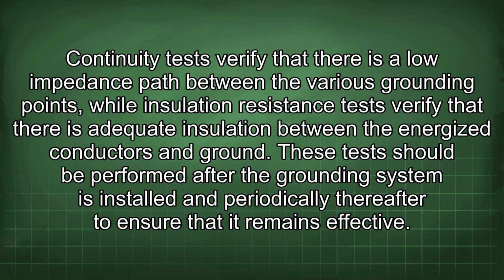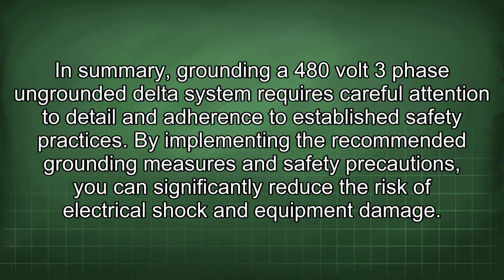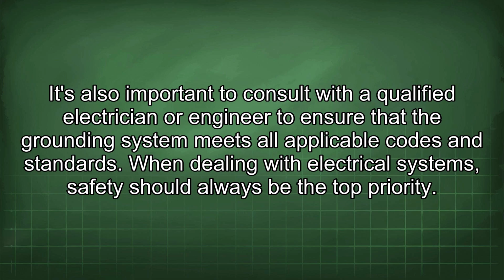These tests should be performed after the grounding system is installed and periodically thereafter to ensure that it remains effective. In summary, grounding a 480 volt 3-phase ungrounded delta system requires careful attention to detail and adherence to established safety practices. By implementing the recommended grounding measures and safety precautions, you can significantly reduce the risk of electrical shock and equipment damage. It's also important to consult with a qualified electrician or engineer to ensure that the grounding system meets all applicable codes and standards.